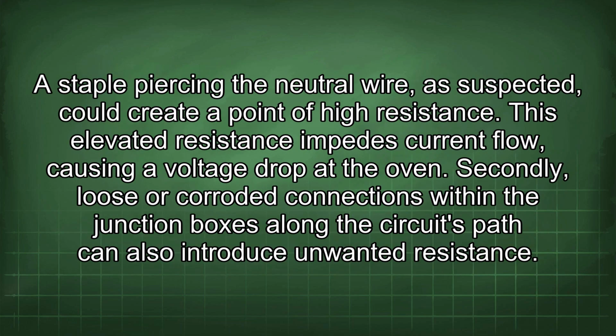A staple piercing the neutral wire, as suspected, could create a point of high resistance. This elevated resistance impedes current flow, causing a voltage drop at the oven. Secondly, loose or corroded connections within the junction boxes along the circuit's path can also introduce unwanted resistance.